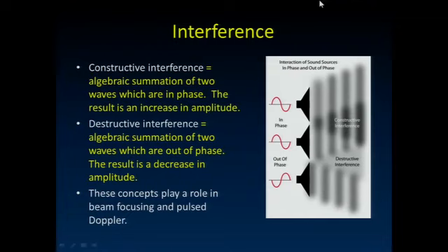I want to mention the fact that ultrasound waves can interfere with each other. And when we think interference, we think primarily of destructive interference, where they kind of cancel each other out. But also there's constructive interference, and we use that to our advantage. On these small phased array transducers, I'm going to stimulate different elements on that array to create pairs and multiple, more than pairs, multiple ultrasound waves that constructively interfere with each other to steer the ultrasound beam, if you will, in a direction that we want to look.